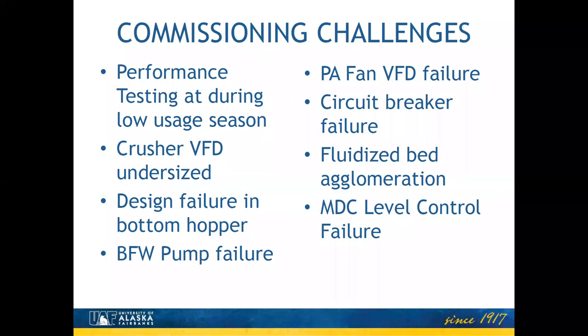So now we're at the point in the project where we're commissioning the new plant, and that's the process of checking the equipment out, making sure it's ready to operate, and then test running it. And we've had a few challenges in this section of it. One of the challenges we identified really early on is that the schedule was driving us towards having to do the performance testing in the boiler, which means we're running at maximum rate and running the steam turbine at maximum rate in the season when UAF has its lowest power and heat demand. And the utilities department and Mike came up with a plan that let us take care of the steam use there. They found places that they can push the steam all around campus, and it's a little risk on their part because while we're testing the new boiler and providing them with large volumes of steam, they're having to turn their old ones way down, so there's not an immediate way to catch it if something goes wrong.